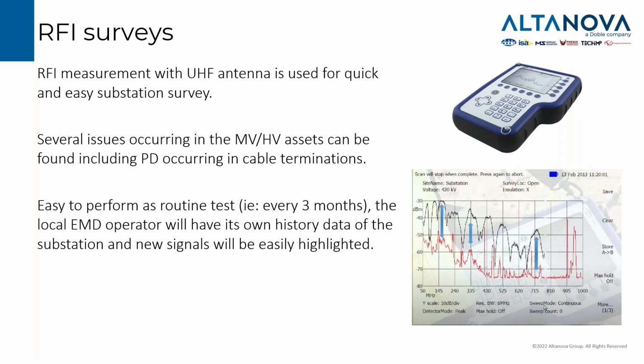A second survey method that we want to present is the RFI survey. It is similar to thermography. It's a practice that is normally performed in substations. It's quite an easy test that can be used as a routine test. And we can find, for example, defects or partial discharge occurring in the cable termination by comparing the spectrum of the baseline with the spectrum nearby the assets.